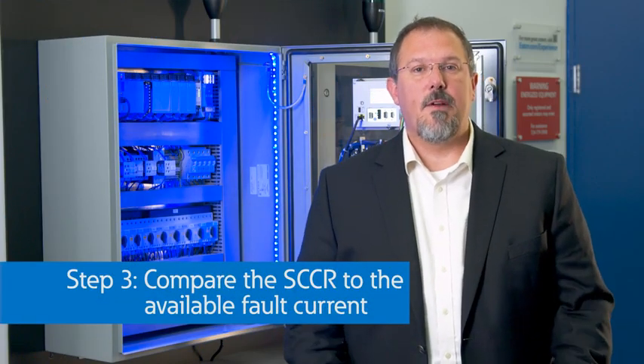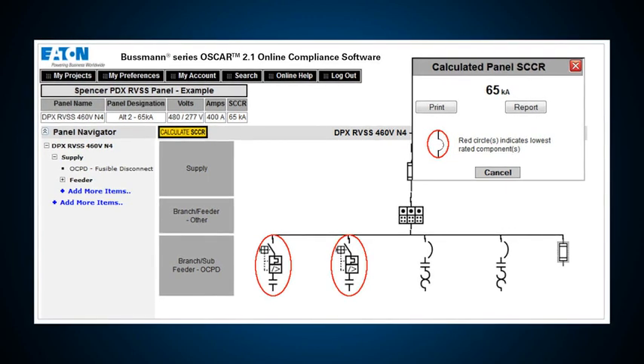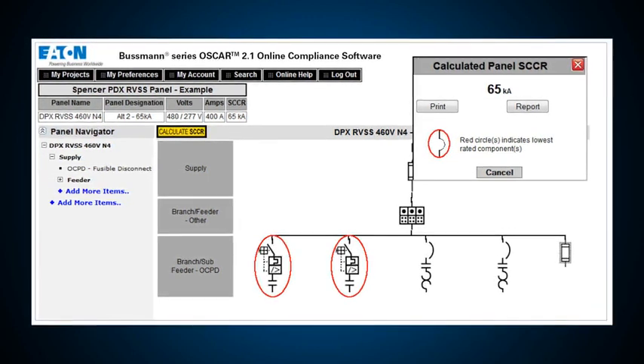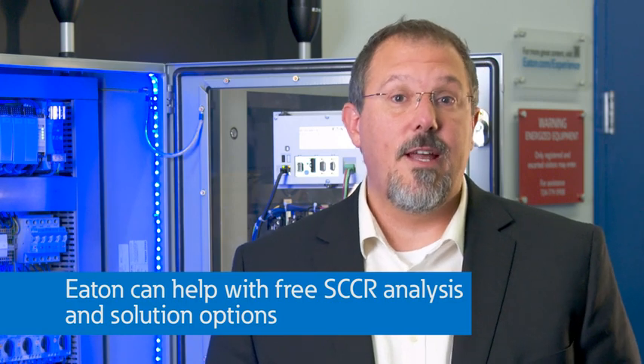Step 3: Compare the SCCR to the available fault current. For end users, specify the right SCCR knowing the available fault current for your facility. For OEMs, applying the rules to calculate the panel SCCR can be challenging — that's where OSCAR comes in. OSCAR is a tool that calculates and documents assembly SCCR for control panels. This helps you validate the proper way to apply the components to reach your new short-circuit current rating. Along with these available tools, Eaton provides free SCCR analysis for your control panel designs, as well as solution options to help you achieve the SCCR you require.